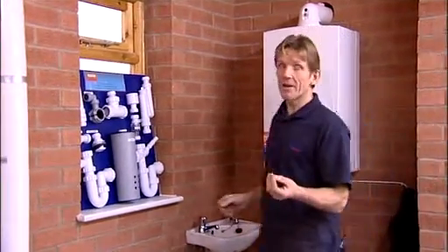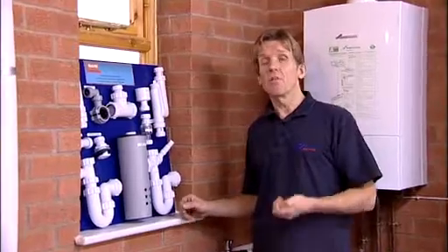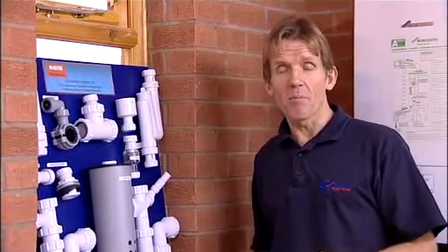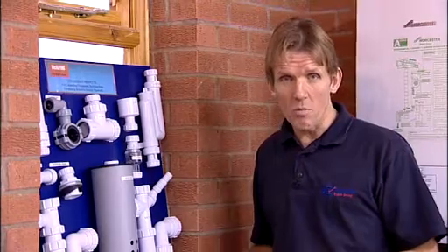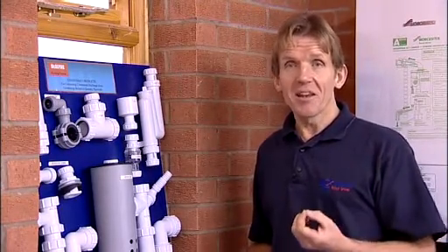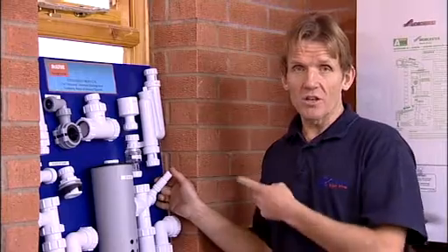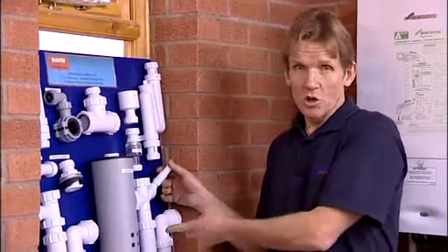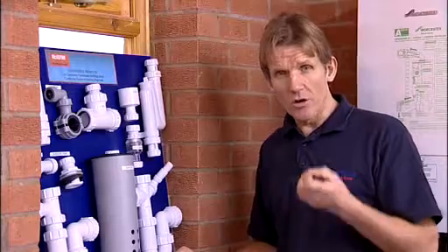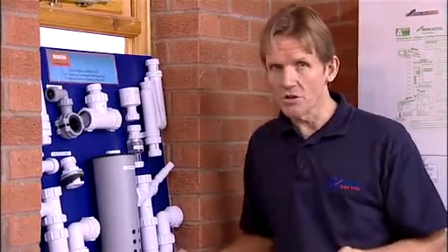But it's where we run it and how we terminate it that makes all the difference. If you get a blockage in the condensate pipe or it freezes up on a cold morning, then you're going to cause a lockout in the boiler. Ideally, you would run the condensate waste internally into an internal trap. If you have to run it externally, make that external run as short as possible and make sure it's insulated.